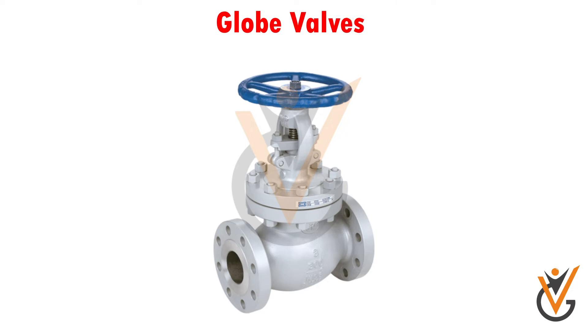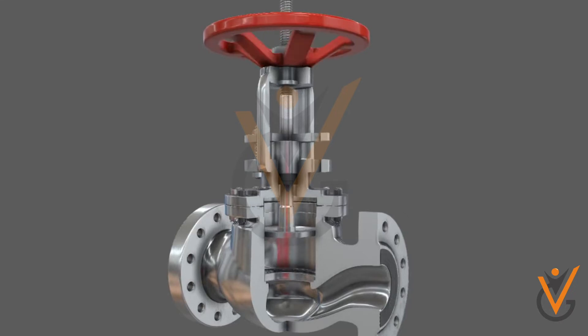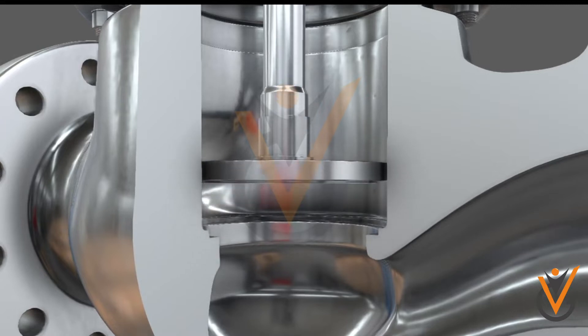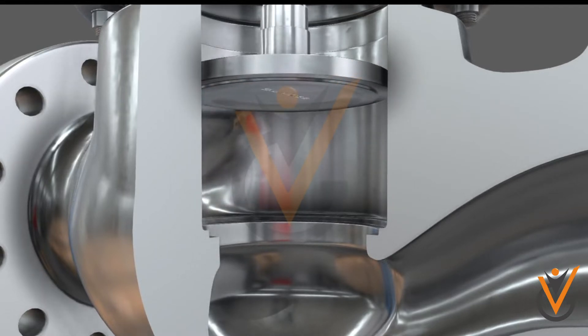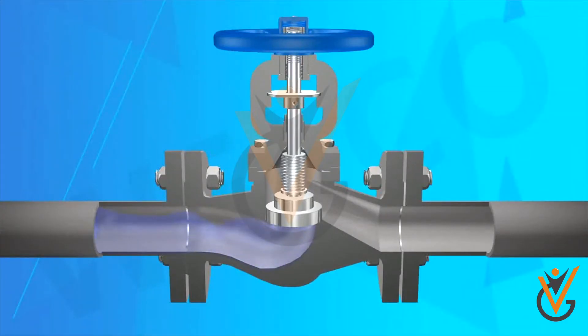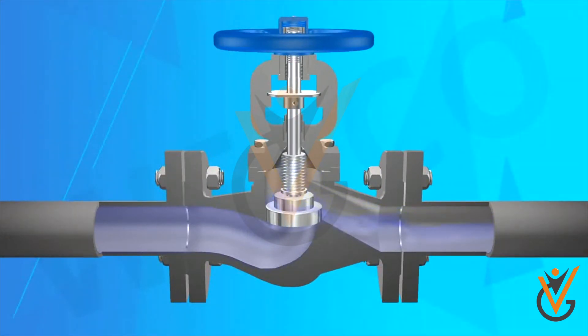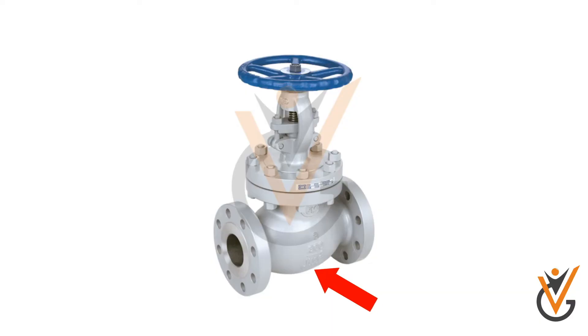Globe valve: used to vary flow accurately and where positive shutoff is required. It is the most common type of valve in the engine room, accommodation, and on deck for general applications of all fluids — oil, water, steam, and air. Available in screwed-down stop valve or screw-down non-return arrangement. A circular disc is lifted or lowered against a valve seat to allow or restrict the flow of fluid. The valve body is globe-shaped with provision of flanges for attachment to pipes.